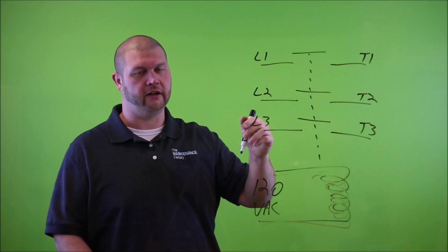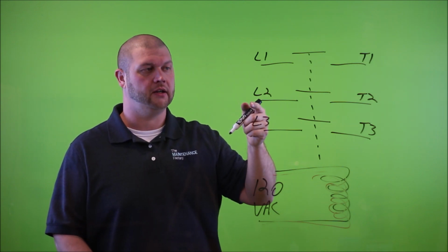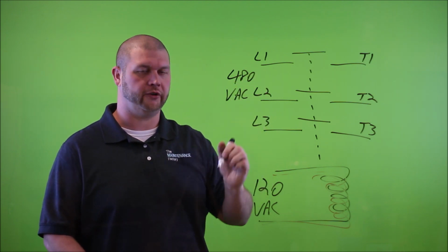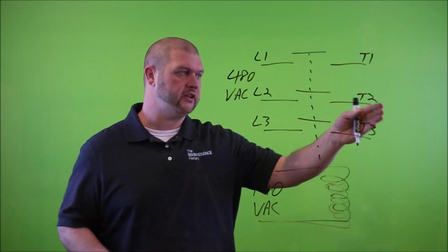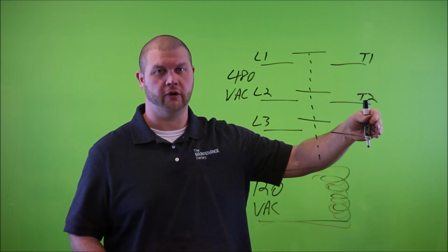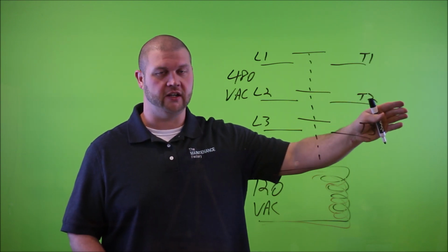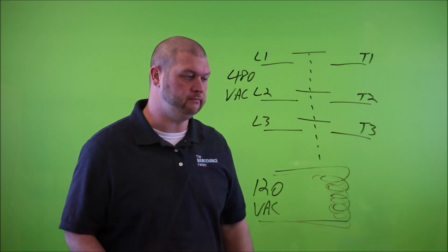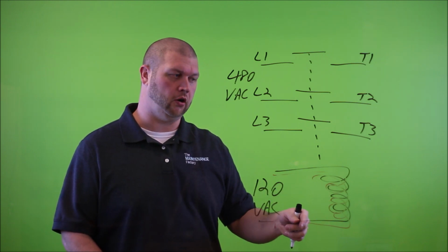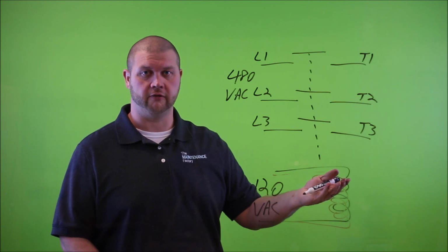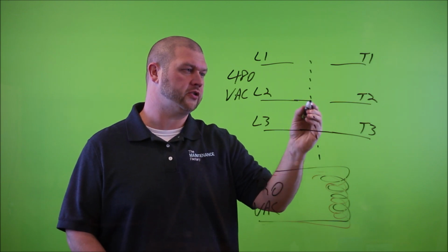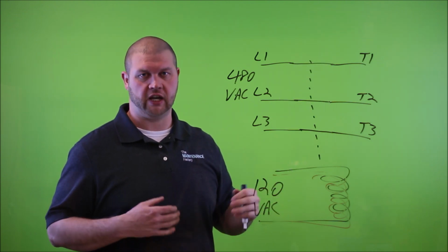On this side here, the L indicates that this is the line side of the contactor, and we'll assume that it's connected to a 480 volts alternating current source. And then on this side, we'll just assume that it's connected to a motor, downstream equipment. It may go to an overload and the motor after that, but this is considered the load side of the contactor. So now imagine that this 120 volts AC coil is now energized, electromagnetic field generated. These contacts are now going to change from the open state to the closed state, and all three are going to change simultaneously.